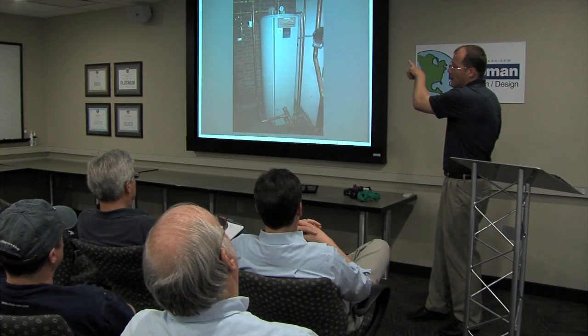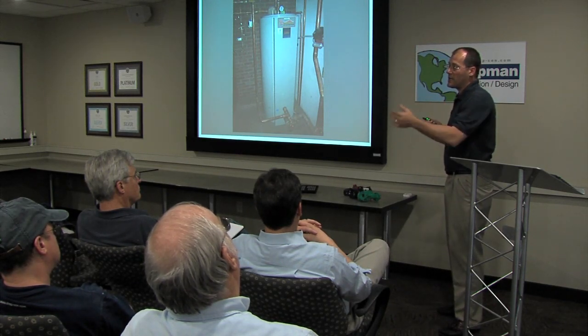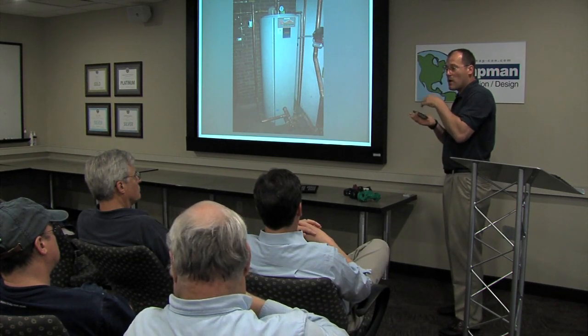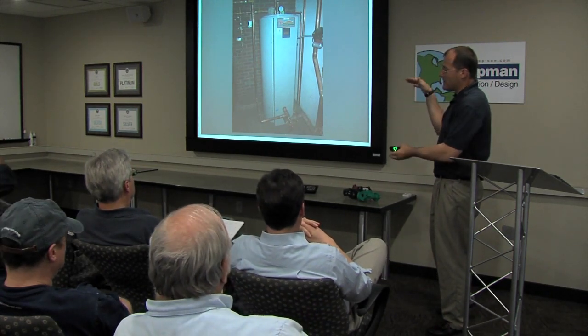So you couple this idea of large thermal boiler water mass with these low mass boilers, and what it solves is the short cycling problem of small water volume boilers with lots of BTUs. You might have a million BTU boiler and a 200,000 BTU load, it's going to short cycle, but give it a 900,000 BTU load and it's going to be happy as can be because it's working on all that water volume. We talked about that hydraulic separator. This is another great new product that's come out since condensing boilers, and it's a great companion.